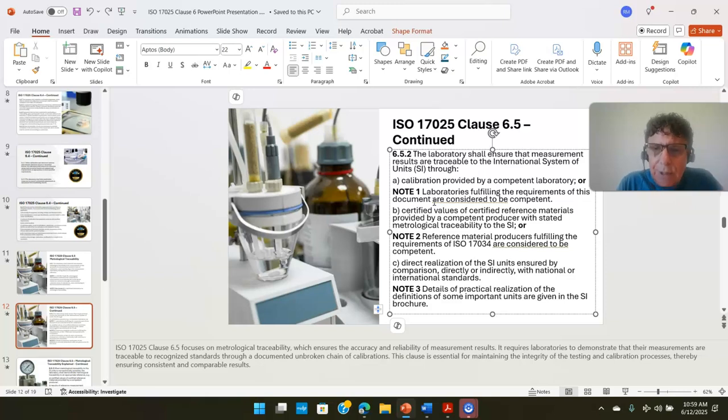The certificate has to say that. It has to have their company's logo, and you need to know who their accreditation body is and what their cert number is. That has to be on the calibration certificate. There's no ands, ifs, or buts about this. If you don't have this on calibration certificates, then you need to get one that does, and you can battle that with your calibration company, but this is what you need to have.